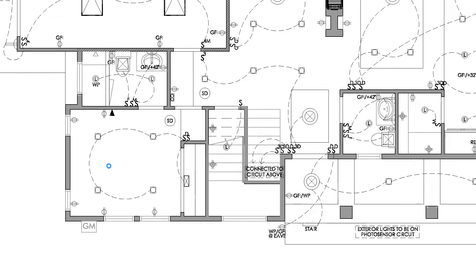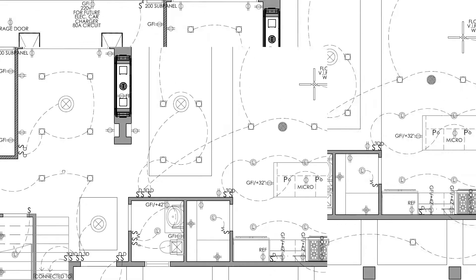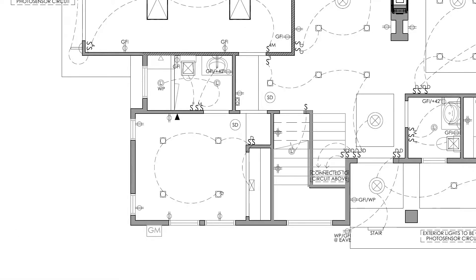As an example, let's go to this bedroom. As we can see, there are these four symbols with a square and a circle inside. If we go to the legend, we can find it here, and we can see that this is for a four-inch recessed downlight. If we go again to the plan, we can see that there is a dashed line here joining these four lights, because these four are in the same circuit. These dashed lines are always going to reflect the circuit.